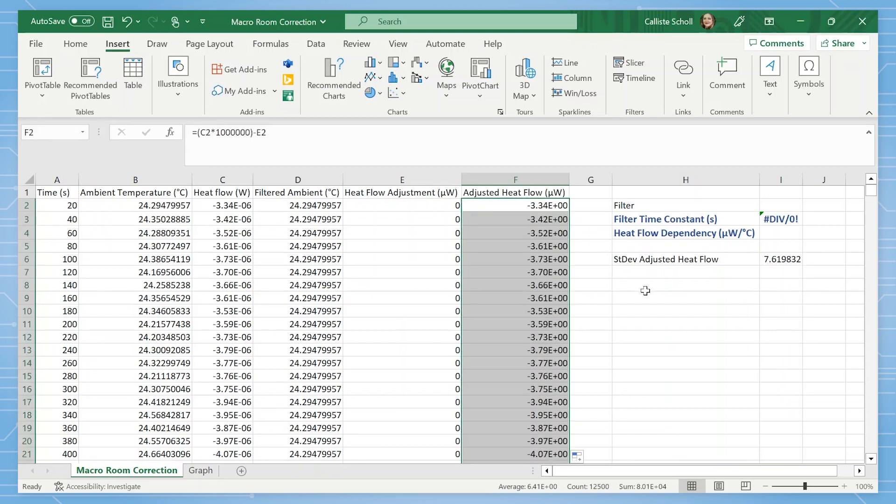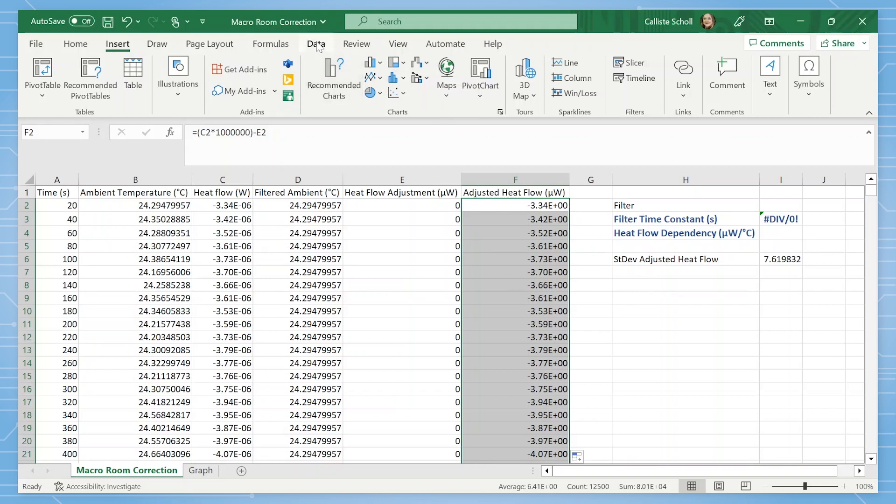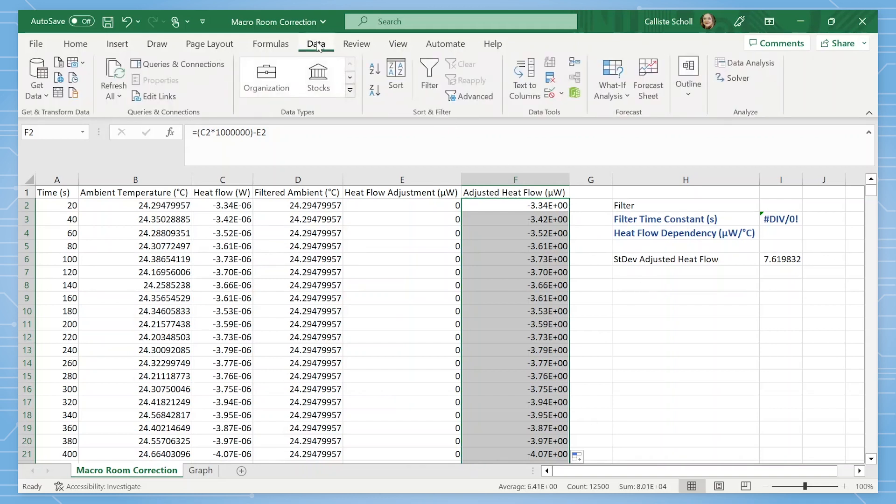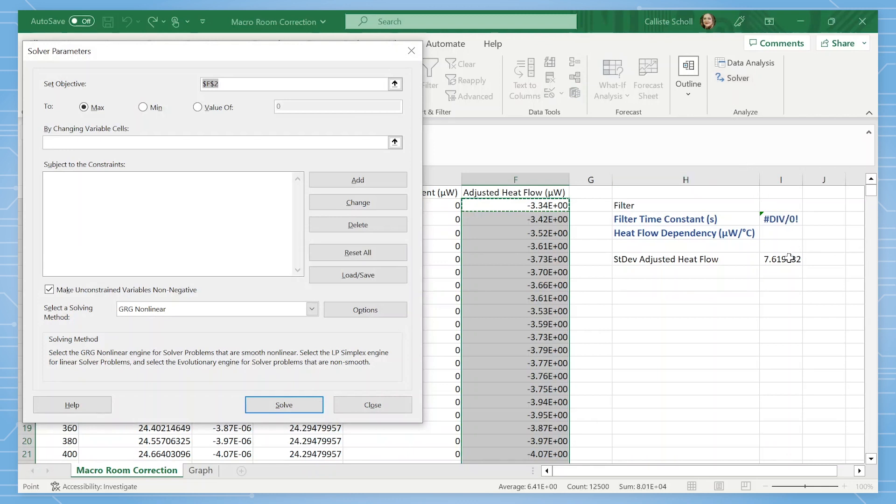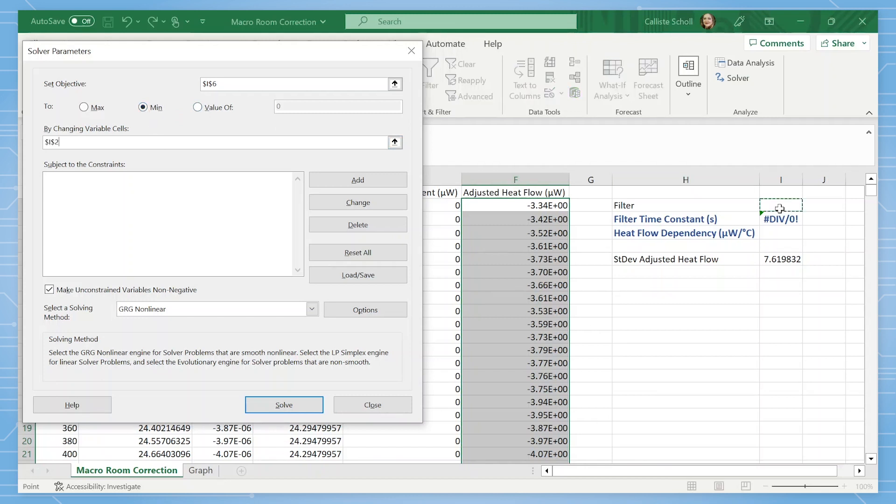Next, we will use the solver add-in to solve for the filter and heat flow dependency values. To solve, we first need to set our objective, which is to minimize the standard deviation of the adjusted heat flow signal. This corresponds to cell I6. And we want to minimize this value by changing both the filter, which is I2, and heat flow dependency I4.